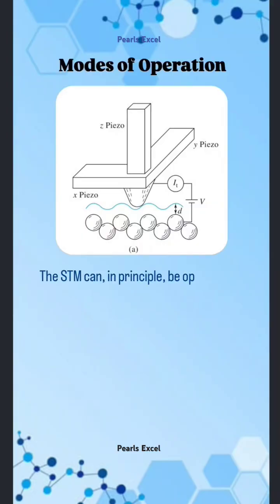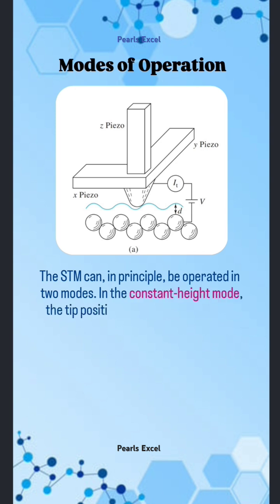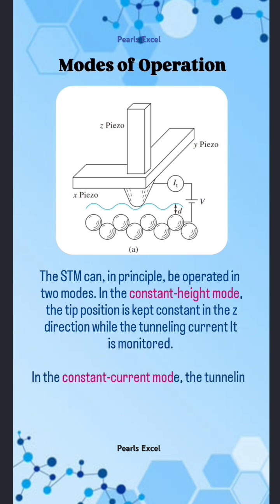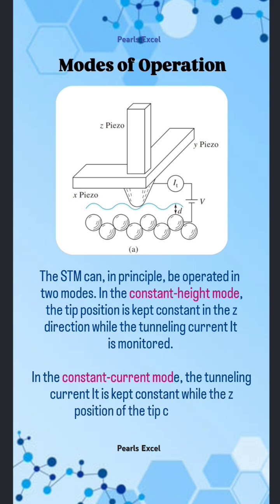Modes of operation: The STM can, in principle, be operated in two modes. In the constant height mode, the tip position is kept constant in the Z direction while the tunneling current is monitored. In the constant current mode, the tunneling current is kept constant while the Z position of the tip changes to maintain a constant current, as shown in the figure.